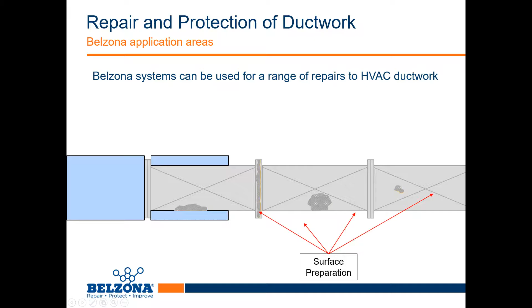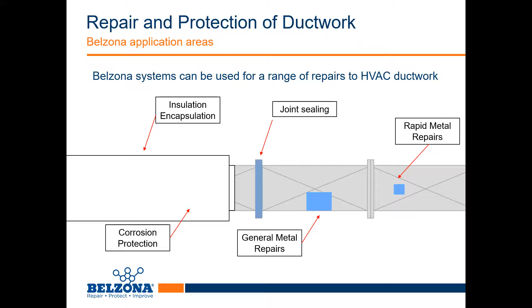Surface prep. You need good metal to bond to, as well as clean it from any type of debris that we've created. And as you can see here, where it's repaired, we're going to come back in with the second coating system. And also we have joint sealing. We're going to seal in those joints and do a complete system. After you've repaired it, protected it, and sealed it in, you know how to repair and refurbish a complete ductwork system.